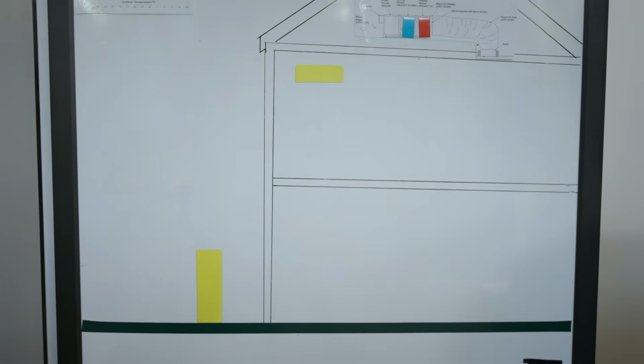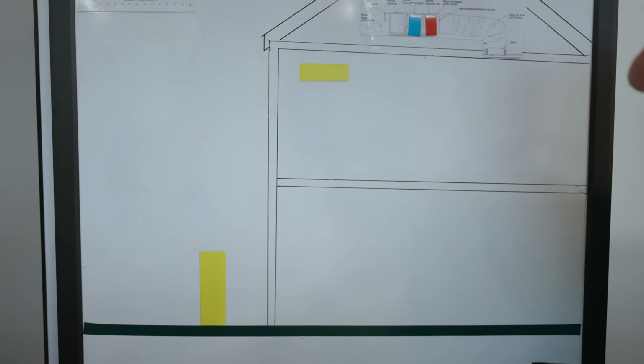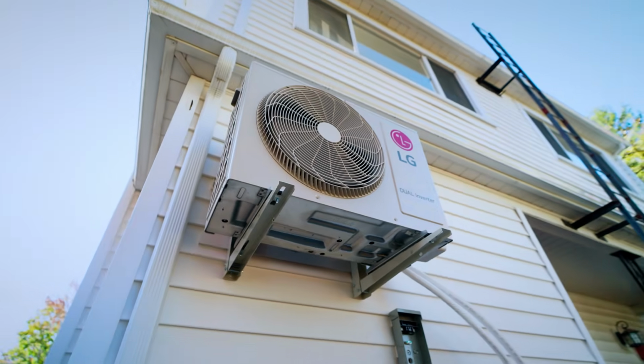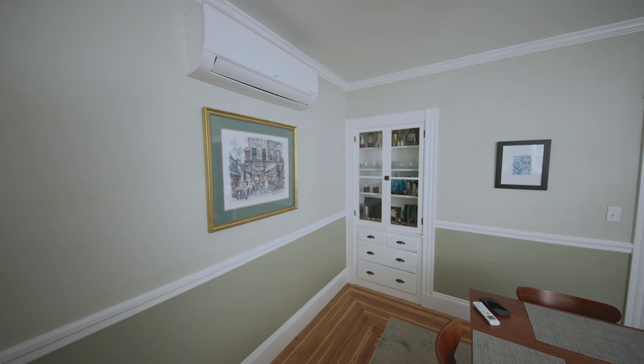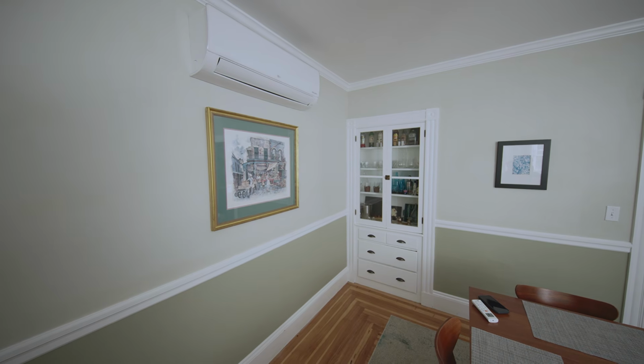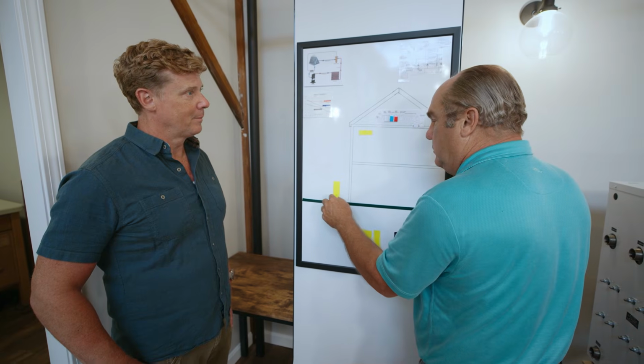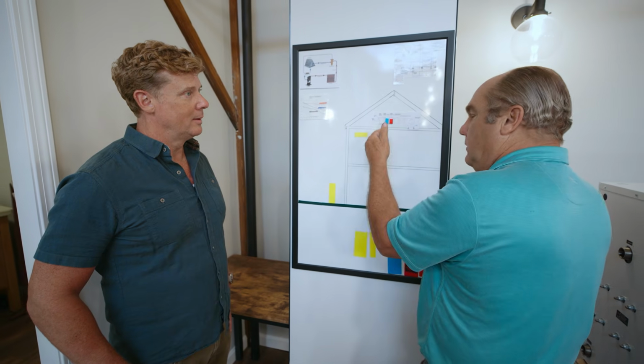Right. The important thing about a heat pump is they all basically work the same. The only question is what is the source of the heat and what's the delivery method? So it's always going to be air to air, air to water, water to water, water to air. So the most common heat pump we know is air to air. You've seen the condensers outside. You'll see the high sidewall units. Often it's just got refrigerant piping between the two, and it either heats or it cools.